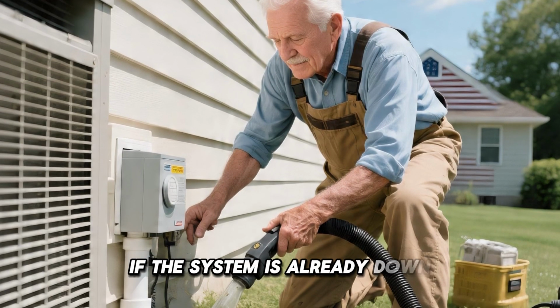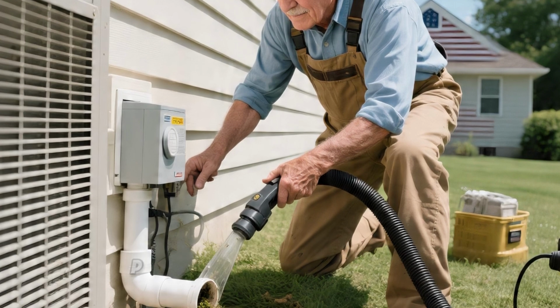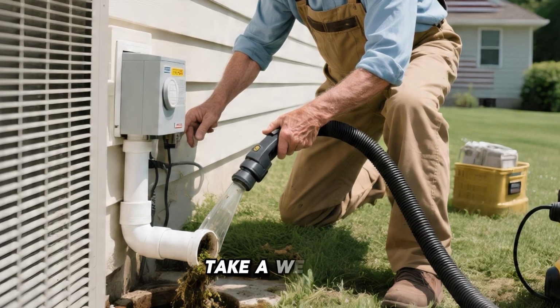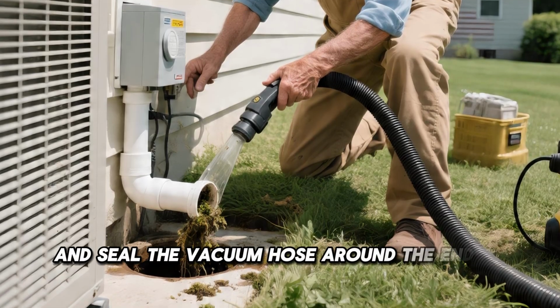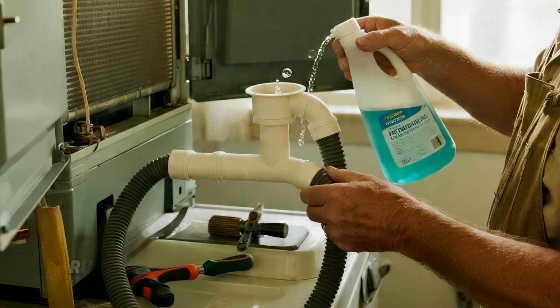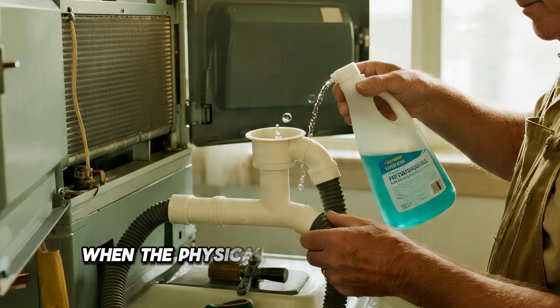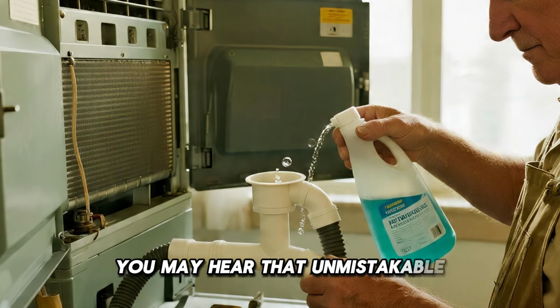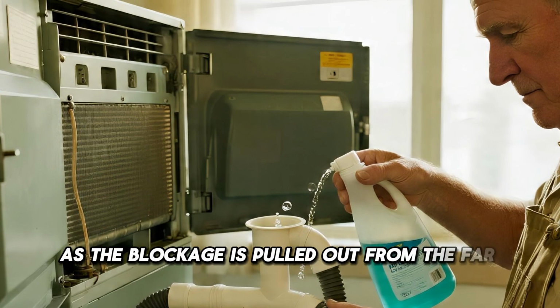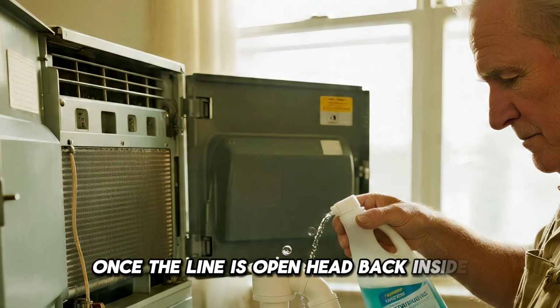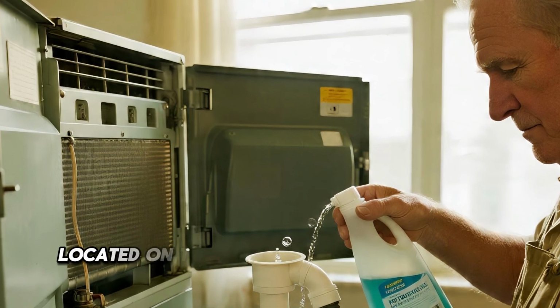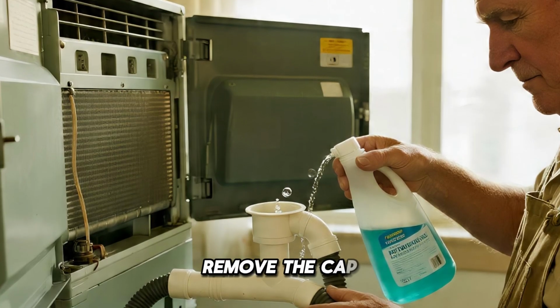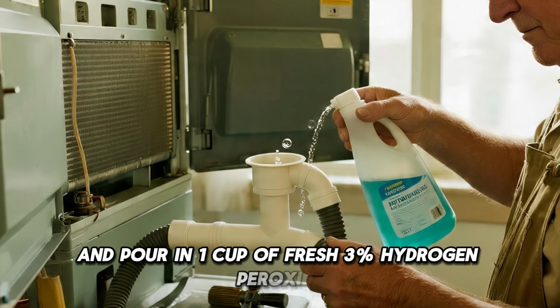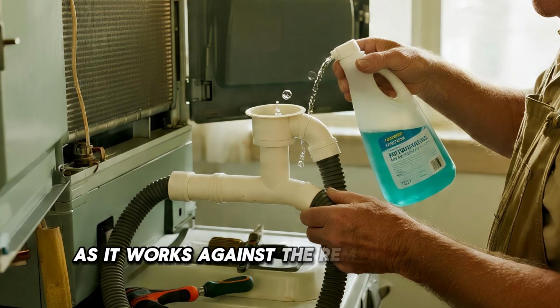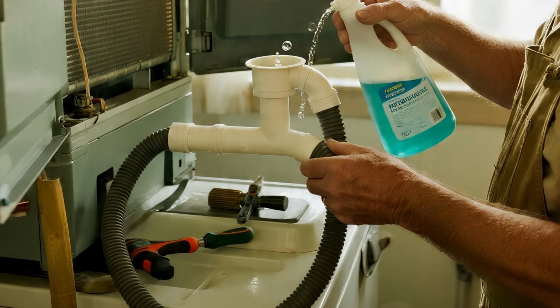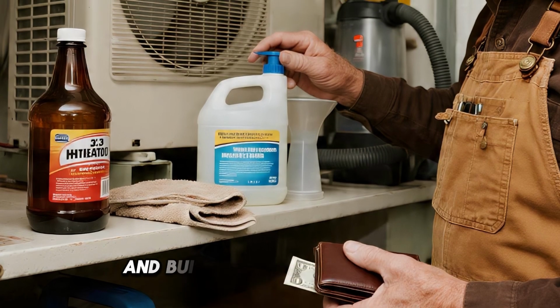If the system is already down, go outside and locate the point where that white PVC drain line exits the house. Take a wet-dry utility vacuum and seal the vacuum hose around the end of the pipe using a rag or your hand. Run the vacuum for 2 or 3 minutes. When the physical clog finally breaks loose, you may hear that unmistakable wet thunk as the blockage is pulled out from the far end. Once the line is open, head back inside. Find the T-shaped access fitting located on the drain pipe near your indoor unit. Remove the cap and pour in 1 cup of fresh 3% hydrogen peroxide. You'll hear the fizz as it works against the remaining living layer clinging to the PVC walls, helping prevent that layer from grabbing more dust and building another blockage.